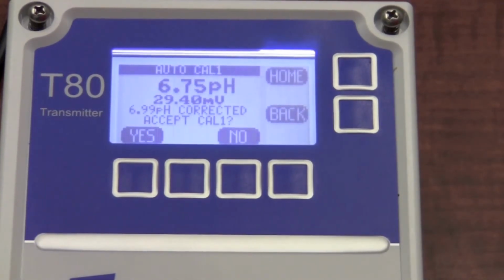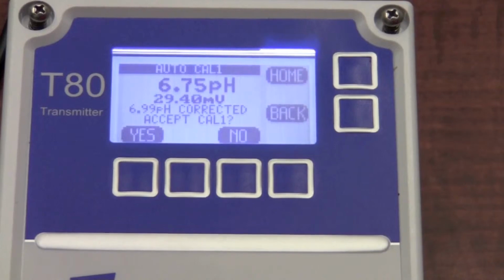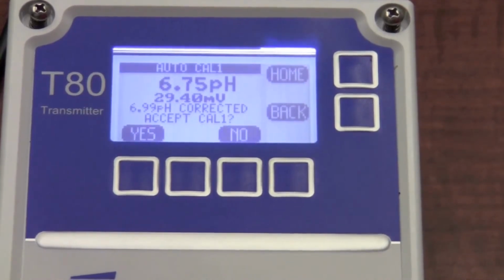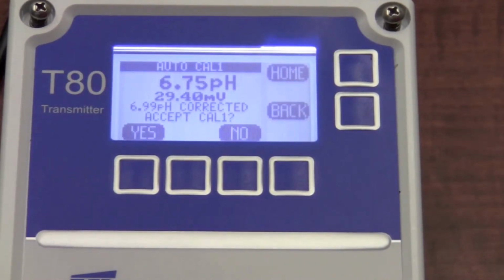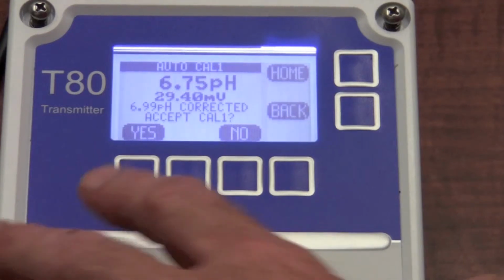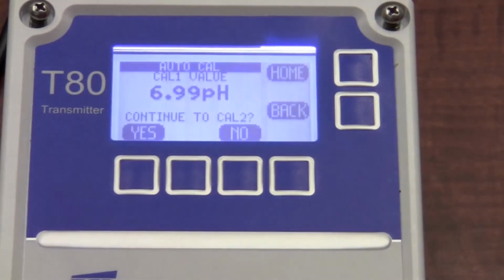Once stabilization has been satisfied, it's going to come up and say this is 6.99 pH, corrected. Do we accept it? If this was a 7 pH buffer, 6.99 is correct. If it's not, if there was another buffer solution you're using and you wanted to correct, it allows you to make a manual entry. For our intents and purposes here, we're going to accept it as yes.